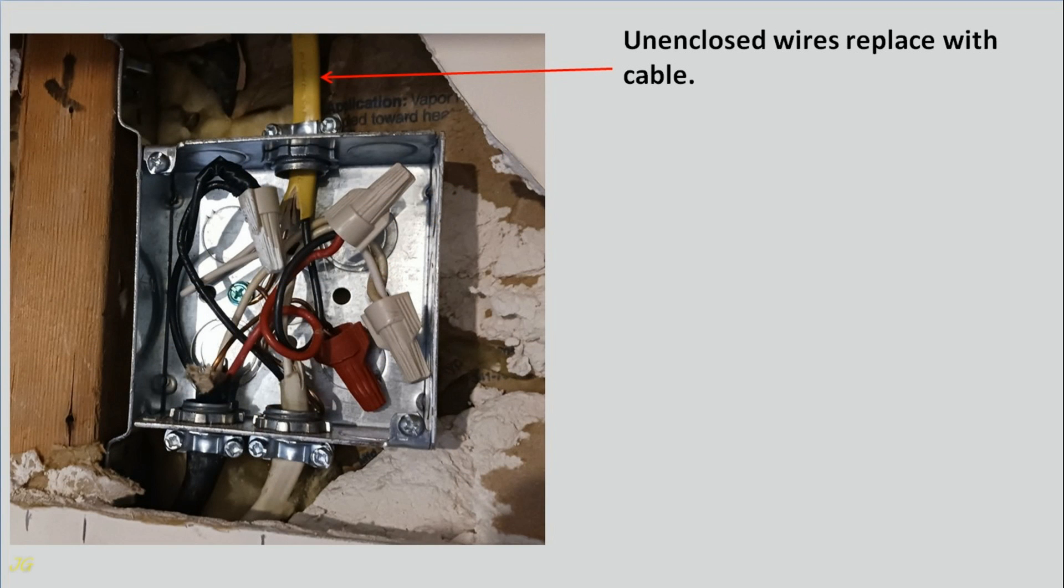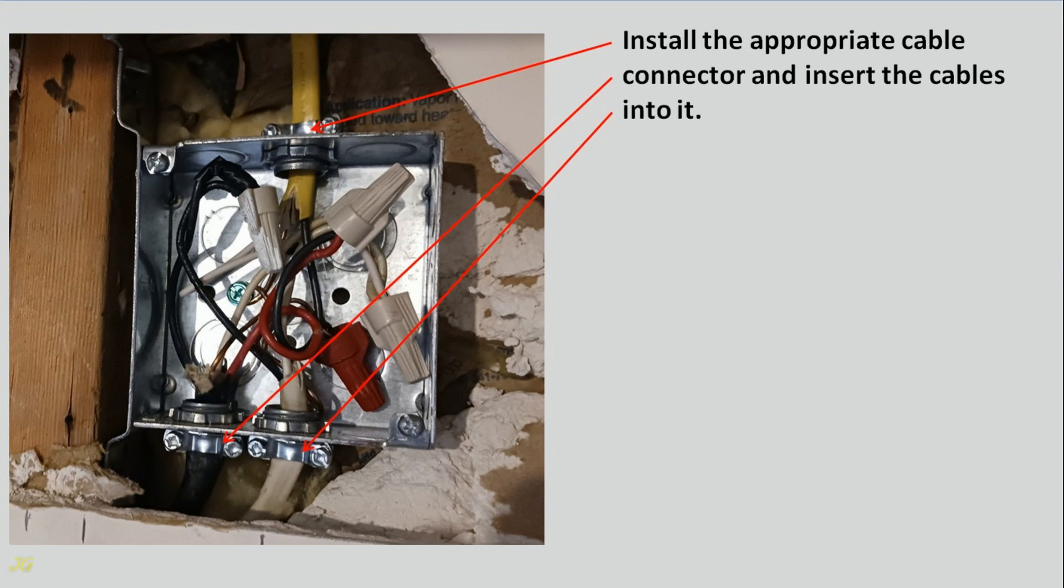Unenclosed wires replace with cable. Install the appropriate cable connector and insert the cables into it. The cable jacket should extend beyond the cable connector at least one quarter inch.